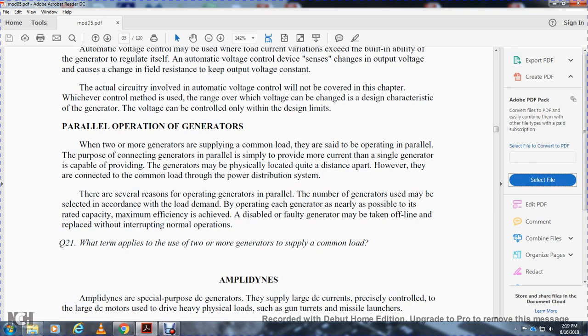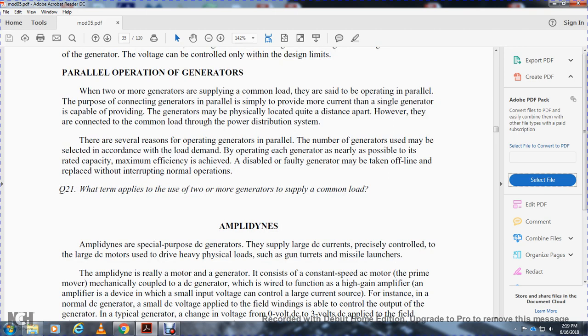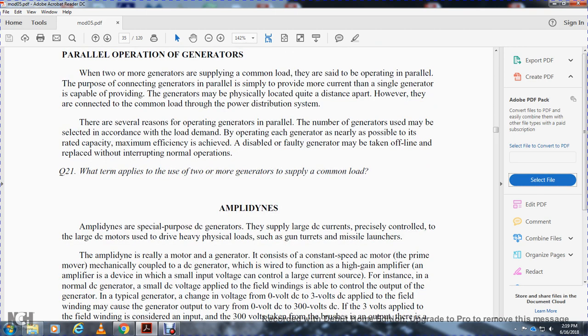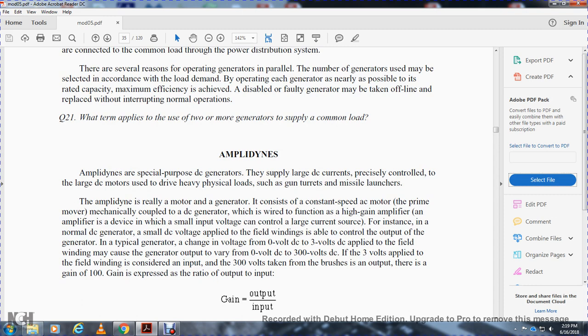Parallel operation of generators: when two or more generators supply a common load, they are said to be operating in parallel. Generators are connected in parallel to provide more current than a single generator is capable of providing, and generators may be physically located in different parts of a system but connected to a common load through the power distribution system. Reasons for operating generators in parallel include: selecting the number of generators to match the load demand so each operates near its rated maximum efficiency; and taking disabled generators offline for repair without interrupting normal operations.